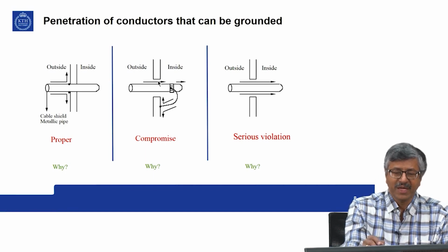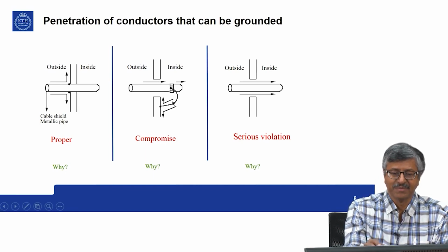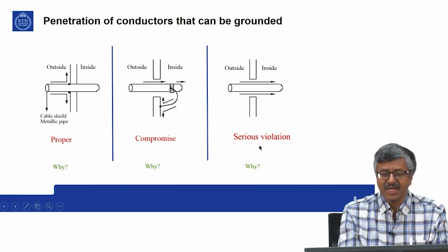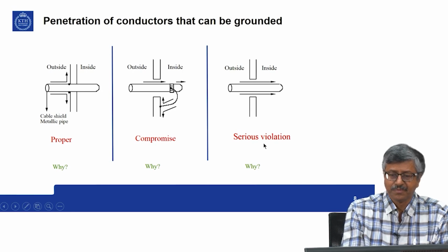So, you can put a metallic strap around, clamp around and connect it to the inside or outside, preferably outside, and this is a serious violation. So, this should never be allowed because there is no zone separation between outside and inside.